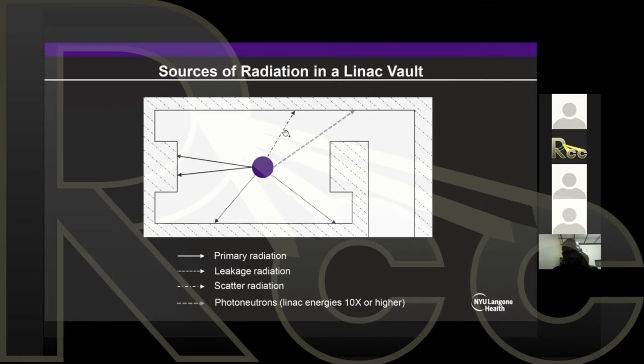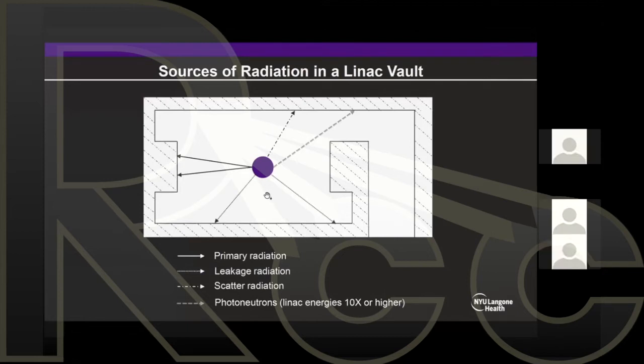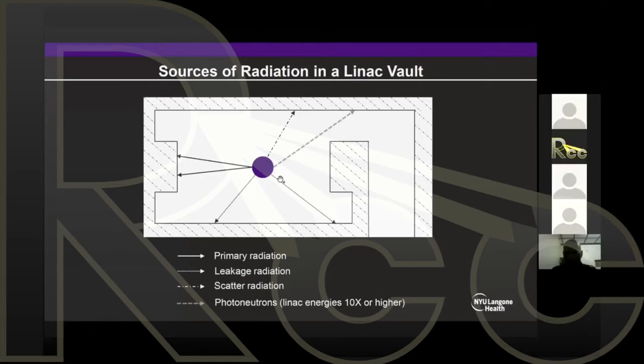You also have scattered radiation. That's gonna be radiation scattering off the patient. So maybe your beam is still pointing to that barrier, but the radiation will scatter in the patient and then go to the secondary barrier. And also photoneutrons, right? For Linac energies higher than 6, normally considered 10x or 10 MV or higher, you're gonna create neutrons, mostly in the Linac head, and those are gonna go isotropically in every direction.